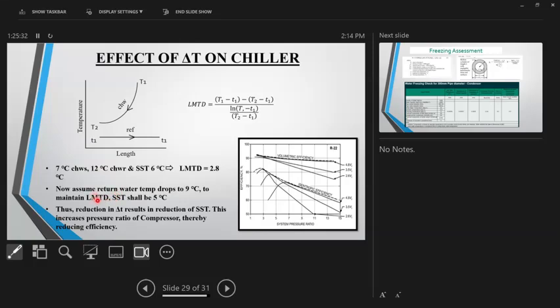Now to maintain the same LMTD, because the heat exchanger designer has designed the heat exchanger for you, for a return water temperature of 9, and to give you 7 chilled water temperature with LMTD of 2.8, you need to boil the refrigerant now at 5 degrees centigrade. For 5 degrees centigrade delta T, you used to boil it at 6 degrees centigrade. But for now 2 degrees centigrade delta T, from 9 to 7, you now need to boil it at 5 degrees centigrade. Which means your compressor is doing now more lift.